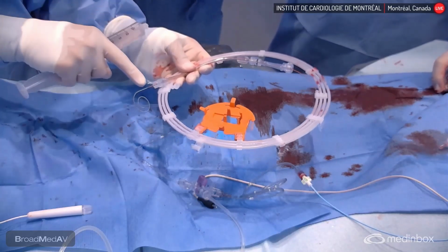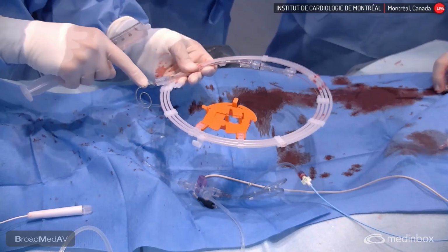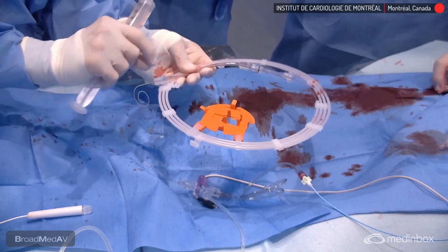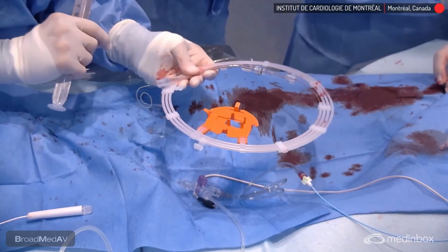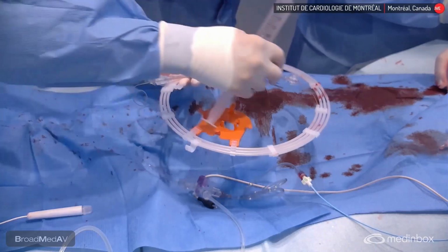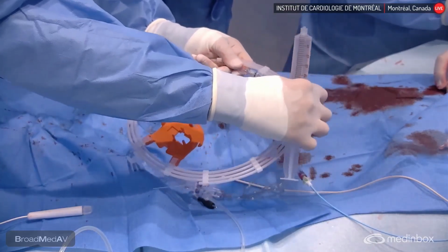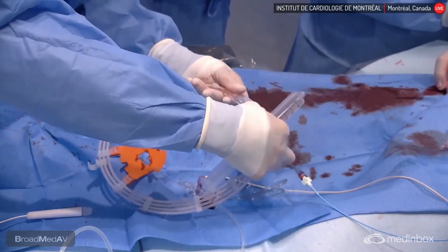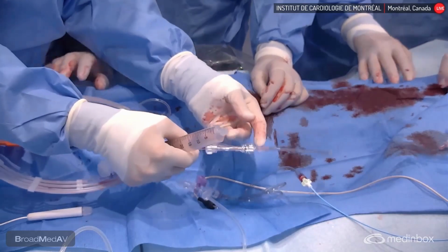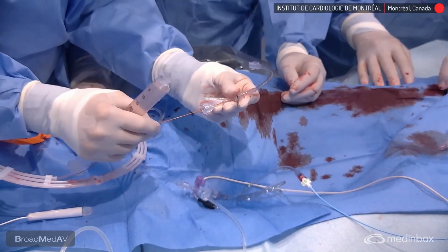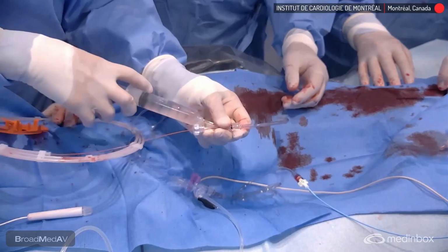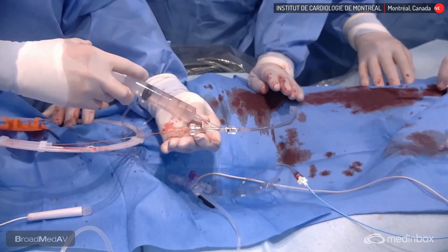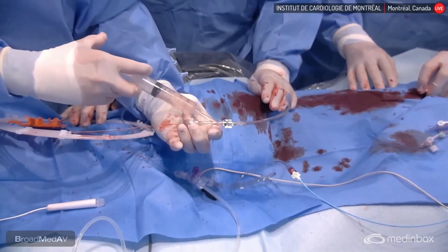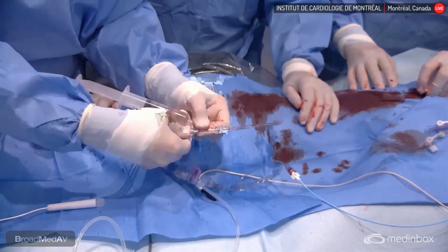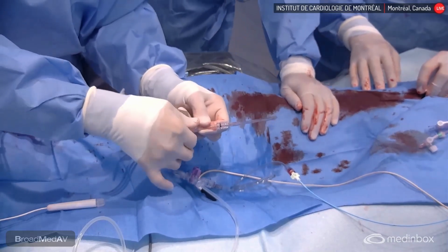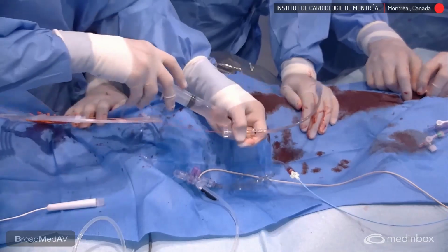And the sensor providing the pressure is at the end of the wire, but at the junction with the insulation, the orange part on the guide wire. So this is the sensor here. So I need to pull back on this wire, flush the wire within the loader. We'll do that now. So I will remove the wire until I reach the junction with the sensor. So we will flush that like this. And then after flushing, I will introduce the wire directly in the ventricle to be able eventually to obtain the LV pressure. So this is flushed now.